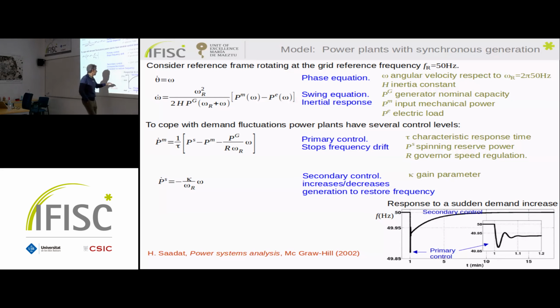But now you have to recover the 50 Hertz. That's what power plants do also with secondary control: you increase the power of the system with a proportionality constant to the frequency deviation, and this restores the frequency to 50 Hertz in a time that depends on the technology of the power plant — could be a few minutes or just one minute, whatever. So if you close it here, you see the primary control oscillates and then stops, and then secondary control recovers the 50 Hertz.